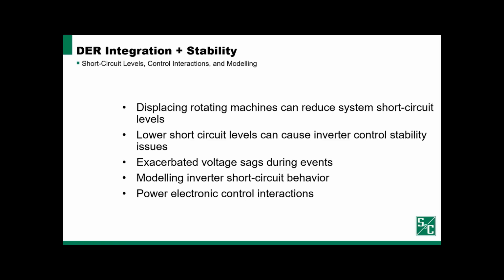As we talked about in the protection section, inverter-based resource short circuit behavior can vary significantly, and the way we've traditionally modeled power systems has to be adapted to account for these different behaviors in inverter-based resources and how they're acting during system dynamics and system short circuits. And finally, we have increasing penetrations of power electronics with these inverter-based resources, which introduces more and more opportunities for the power electronic controls to interact with one another, which is something we must ensure that we're looking for in our models as well as our system operations, to ensure we maintain stable operation and are cognizant of possible control interactions between resources.